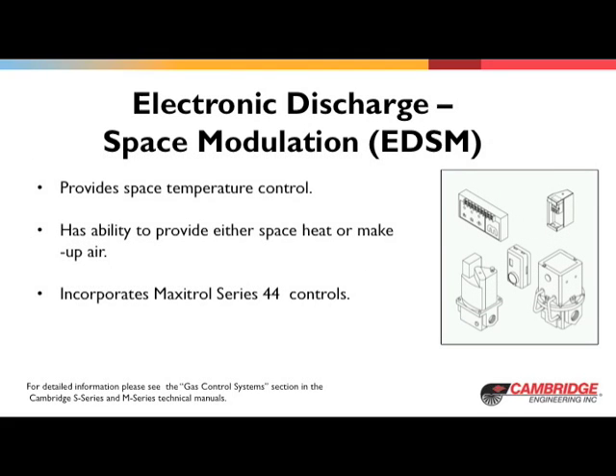Electronic Discharge Space Modulation, or EDSM. The EDSM control system may be used on both S- and M-series products. EDSM provides space temperature control. The discharge temperature of the heater modulates based on a Space Temperature Selector Setpoint, or STS. EDSM has the ability to provide both space heat and make-up air. The STS setting determines the heater's discharge. The STS is mounted in the space and part of the EDSM control system. The STS senses the space temperature and communicates a resistance signal back to the amplifier that corresponds to the temperature variation from the STS setting.